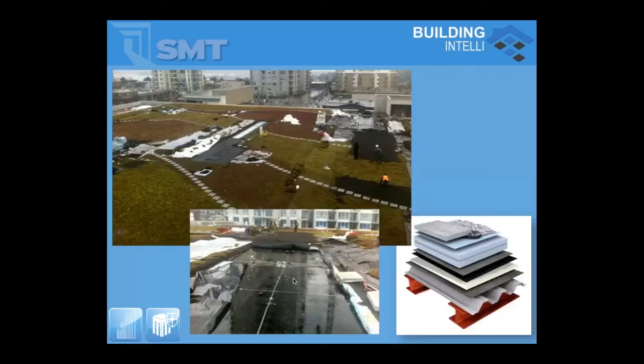On this particular project, we got a phone call later, after the green roof had been planted, that there were about 1,000 holes within the membrane. It turned out the electrical contractor had gone in and put his conduit on the underside of the metal deck, drilling up with three-quarter-inch screws through the gypsum board and through the membrane, puncturing it. He'd been using three-quarter-inch screws for decades — changed the assembly, small detail — and we had a perfect storm for a large insurance payout from his insurer. If it wasn't that, it would have been the signage contractor or the CCTV guy drilling up through the assembly.